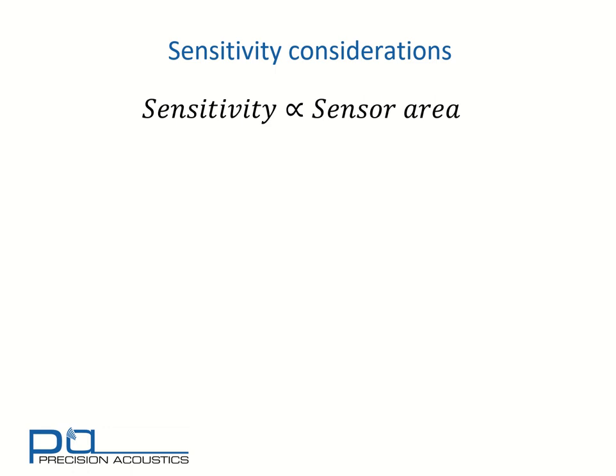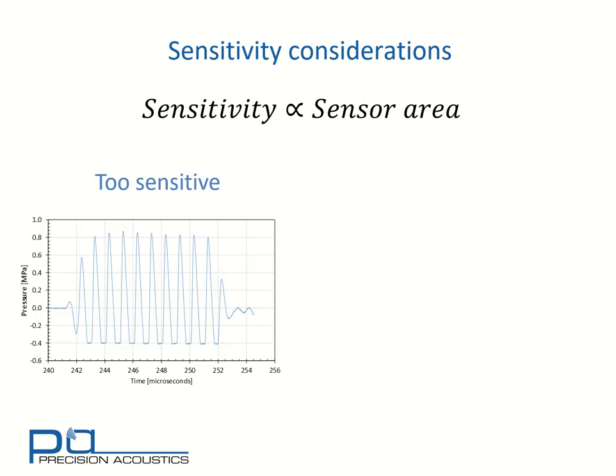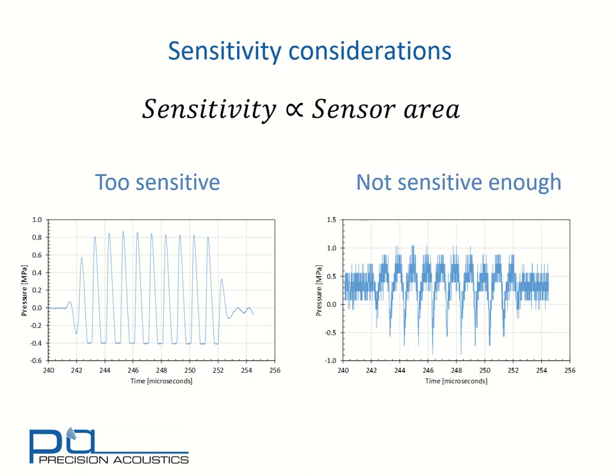Generally speaking, sensitivity is proportional to sensor area. When a hydrophone is too sensitive relative to the field being measured, saturation can occur. This can clearly be seen from the clipping on the peak negative excursion of the waveform shown on the left hand side. Similarly, when we have insufficient sensitivity, we can have a noise limited measurement, where noise is masking the underpinning acoustic signal.